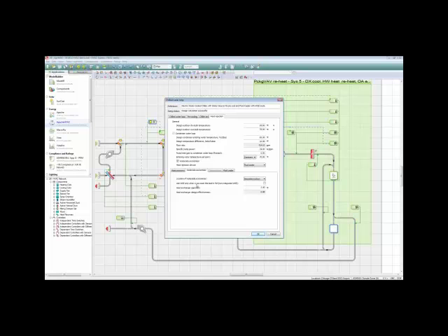And so as long as it can do something useful to reject part of the load, and collectively it's not taking too much of the heat rejection capacity away from the condenser tube bundle, at which point either the outdoor conditions become too severe or the load is too high, it will no longer be useful.